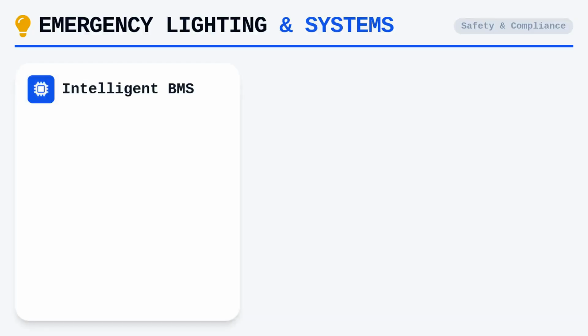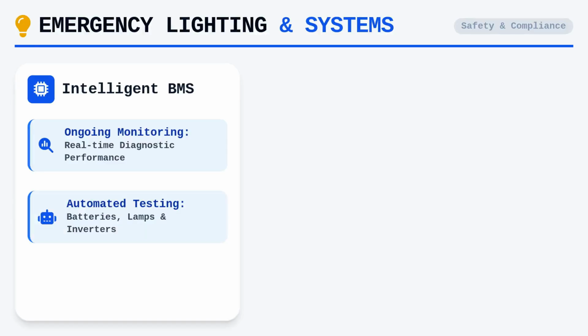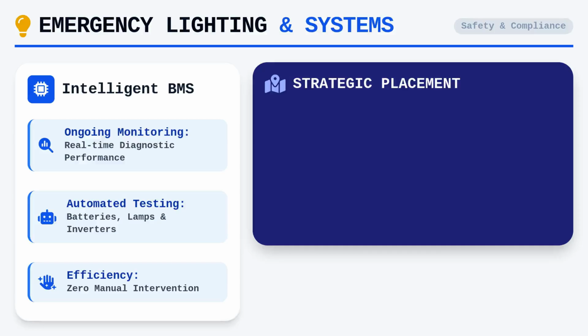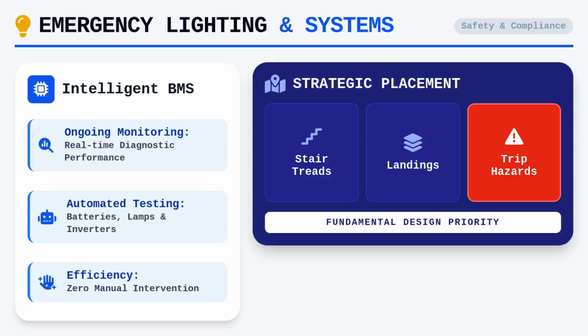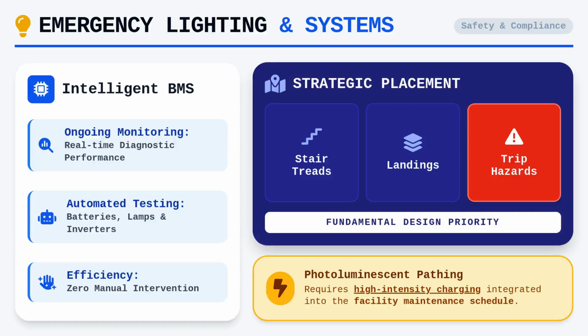In modern complex environments, the integration of emergency lighting with intelligent building management systems offers significant advantages for ongoing monitoring and diagnostic performance. These systems can provide automated testing protocols, which are required periodically to ensure that battery modules, lamps, and inverters are operational without requiring manual intervention for every inspection. However, even with advanced automation, physical placement remains a matter of sound fundamental design. You must ensure that luminaires are strategically positioned to illuminate stair treads, landings, and obstacles that might pose a trip hazard. If you are relying on photoluminescent materials for pathway marking, they must be periodically charged by a high-intensity light source to function effectively, and this requirement must be integrated into the maintenance schedule of the facility as a whole.